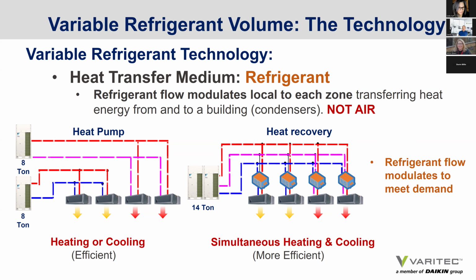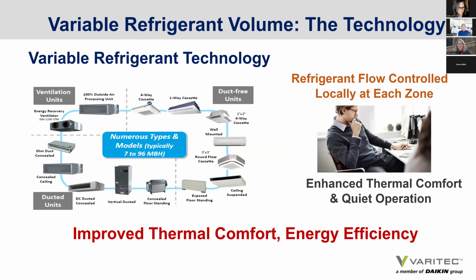A more efficient approach to that technology is a heat recovery technology. Our manufacturer, Daikin, uses a three-pipe system where you can provide simultaneous heating and cooling off of a common condenser. That adds a layer of efficiency because you're actually distributing heat energy in the refrigerant itself to the appropriate zone depending on the demand, without having to deliver it all the way back to the condensing unit, which requires energy to do so. So supplying that refrigerant locally to each zone, we bring refrigerant to the evaporator coils in discrete cassettes, either in each zone through ceiling and wall cassettes, or we can provide ducted technologies that are ducted to two or three zones to a variable refrigerant fan coil. And in most conventional systems, we handle the latent and sensible cooling and heating requirements at these fan coil units.